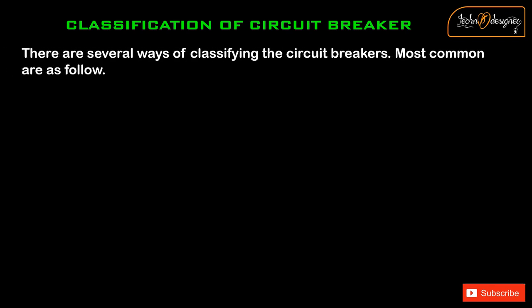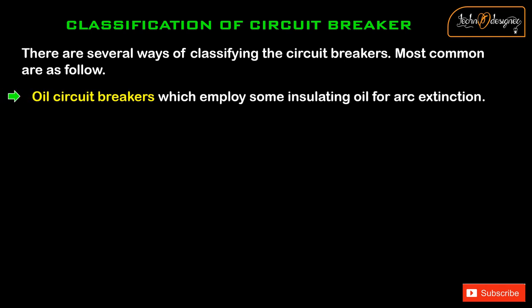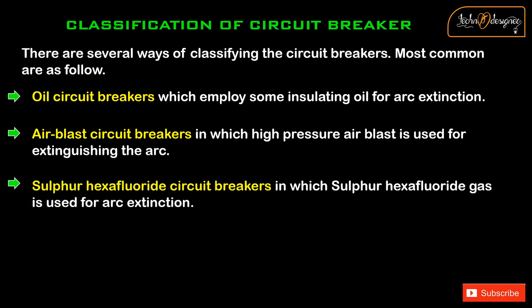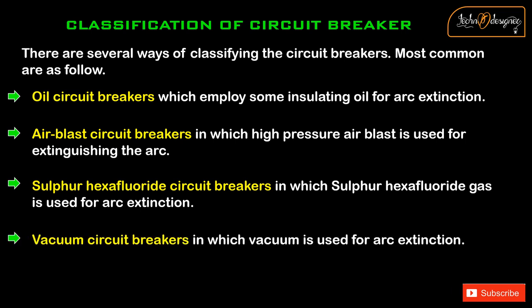Classification of circuit breakers: There are several ways of classifying circuit breakers; the most common are as follows. Oil circuit breakers, which employ some insulating oil for arc extinction. Air blast circuit breakers, in which high pressure air blast is used for extinguishing the arc. Sulfur hexafluoride (SF6) circuit breakers, in which sulfur hexafluoride gas is used for arc extinction. Vacuum circuit breakers, in which vacuum is used for arc extinction.